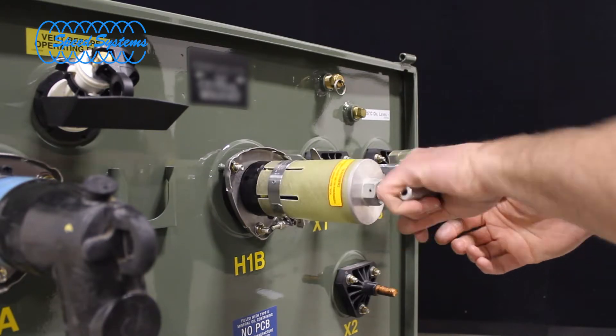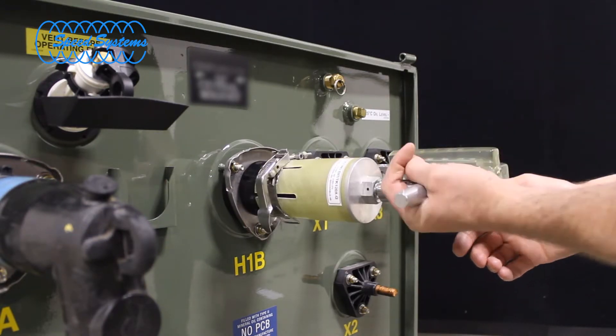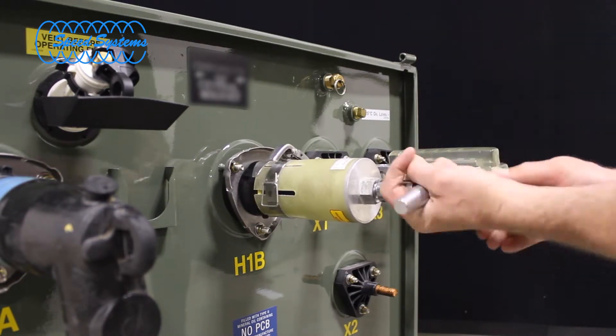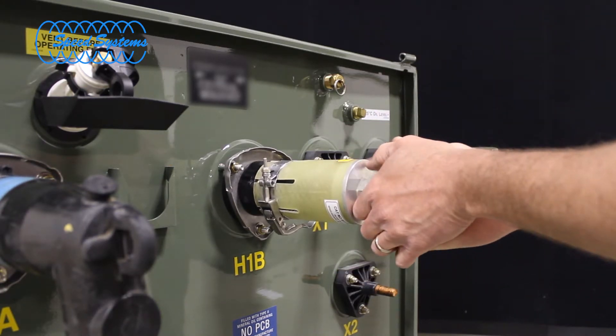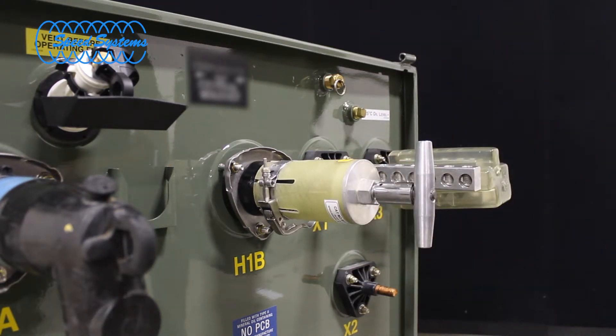Rotate the tool clockwise until the torque limiter pops. The torque limiter may pop several times during the final stages of tightening. Keep rotating the tool until the torque limiter has popped several times without further rotation of the insert.